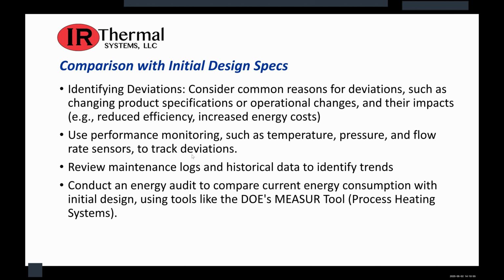So, comparison with original design specs, you want to identify any deviations. Consider common reasons for deviations, such as changing product specifications or operational challenges and their impacts. That can also reduce efficiency or increase energy costs. Use performance monitoring such as temperature, pressure, and flow rate sensors to track deviations, and review your maintenance logs and historical data to identify trends. You also might want to consider conducting an energy audit to compare current energy consumption with the initial design, using tools like the DOE's MEASUR Tool for process heating systems.